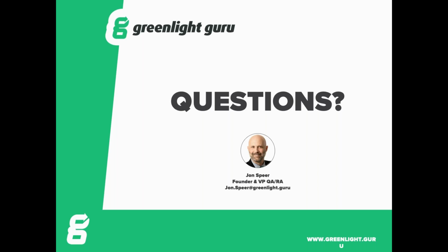All right, so Jim asked, and this is a lengthy question, so bear with me, folks. On slide 29, design inputs should be stated in a measurable way. Do all design inputs need to be measurable, or is verifiable a more accurate description in some cases? Really good point, Jim. Verifiable is really what we're going for. I guess it doesn't technically have to be, quote, measurable, but you definitely need to state it in terms that it's verifiable. So really good. Thanks for pointing that out. Very helpful.